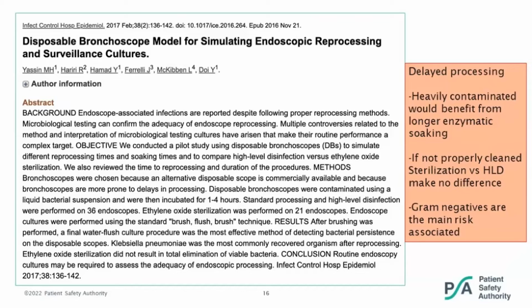Delayed processing was really the most important aspect in having a positive culture. The scopes that were processed within 1 hour, all of them were clean. Of the scopes that were processed after 4 hours, for a significant number of them, we failed in cleaning them. Second, if you have a scope that's heavily contaminated or has delayed processing, you have to work with your endoscopy suite processing to make sure that they soak these scopes in the enzymatic cleaning for a longer period. Typically, the manufacturer says around 10 minutes, and for heavily contaminated or blood or delayed processing, we're talking about 30 minutes or more. I don't think this is done that way routinely, but this has to be stressed for any delay.